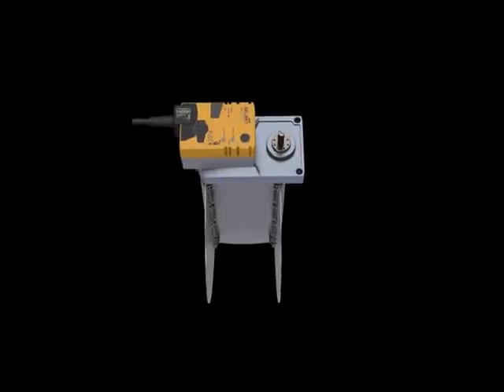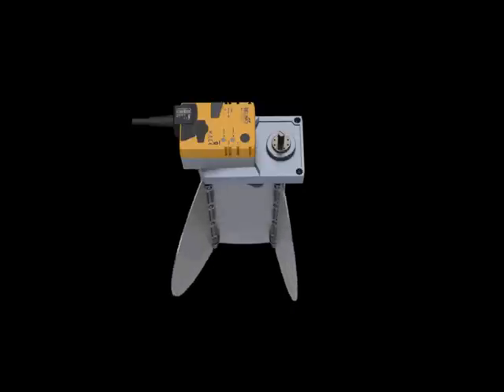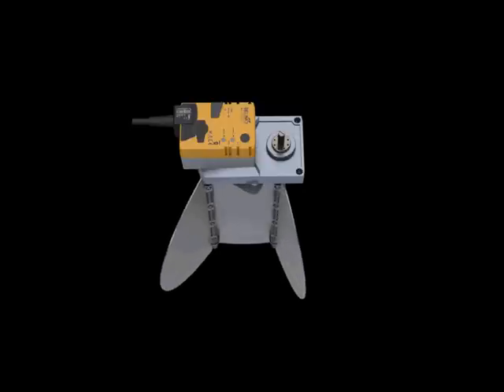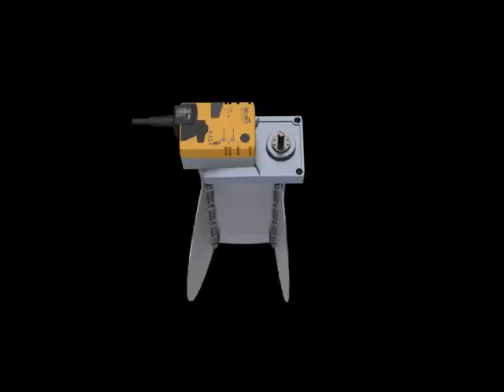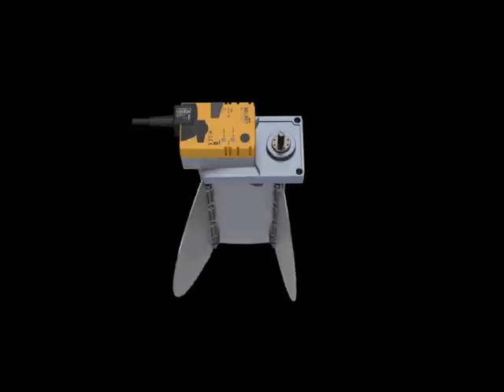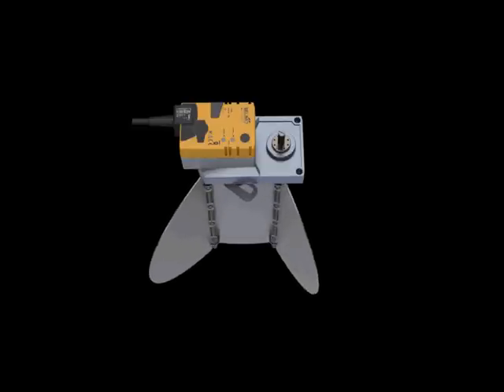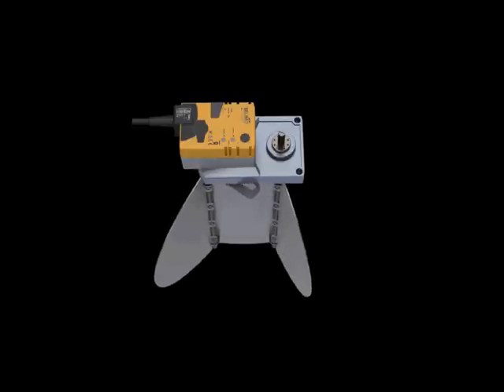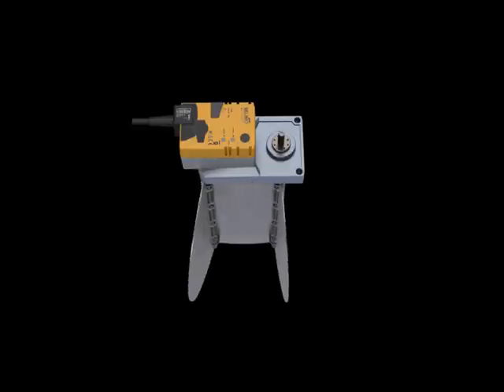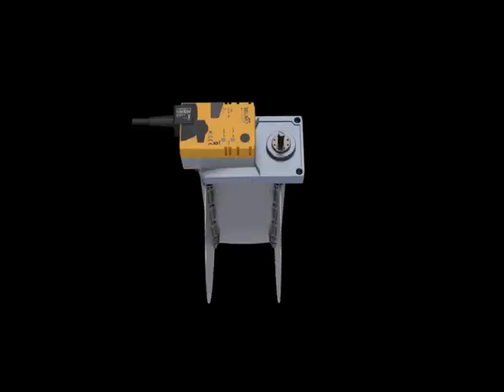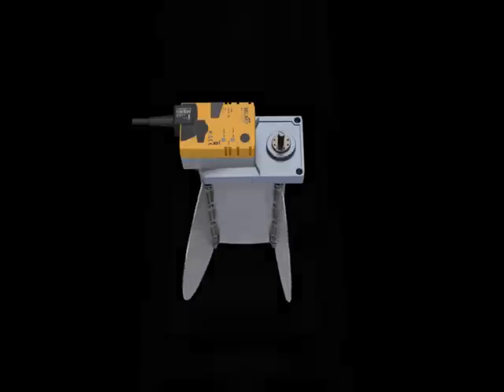Unlike conventional dampers which require a full 90 degrees of swing, the AccuValve's control blades require only 45 degrees of swing for full open to full closed.